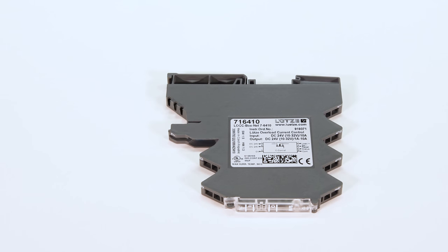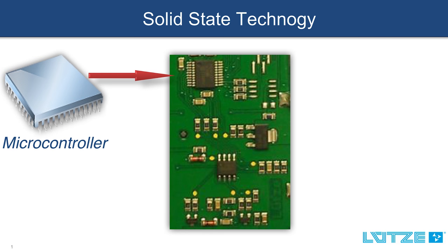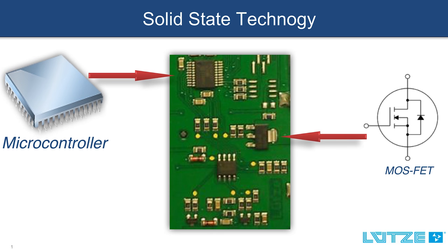So how is the LOCC-Box different from this technology? The LOCC-Box resolves all of the inherent performance issues of fuses and circuit breakers by utilizing solid state technology. A microcontroller is measuring the voltage and amperage while the MOSFET is controlling the on-off function, which are two key pieces of the solid state technology. By implementing solid state technology into the LOCC-Box, we are able to achieve the following benefits when it comes to protecting control devices.